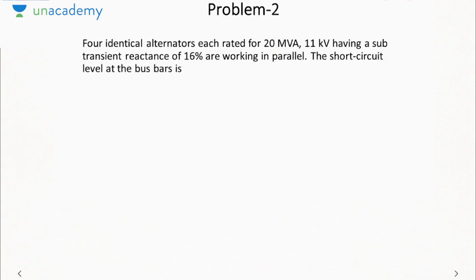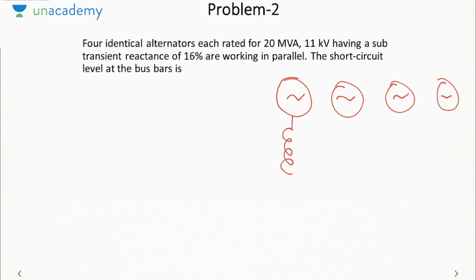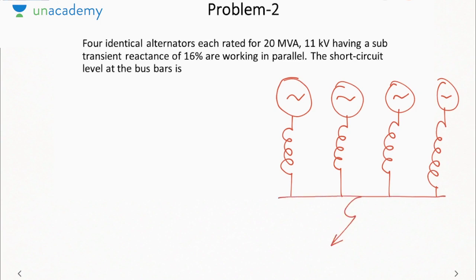It is saying 4 identical alternators, each rated 20 MVA 11 kV, having subtransient reactance 16%, are operating in parallel. So how does the system look? These are 4 alternators. These are their reactances, and all are operating in parallel. It is asking the short circuit level at the bus bars. Now we will assume no load condition. So in general we will assume 1 angle 0 as the EMF. The reactance of each generator is 0.16 pu.